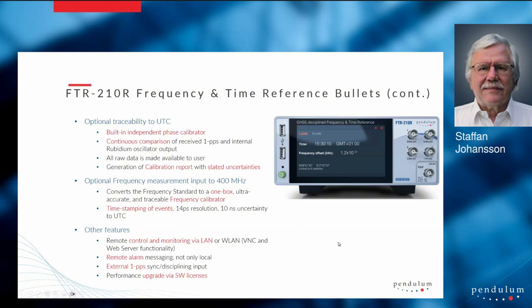There are other important bullets to mention, most of all the optional traceability to UTC, because this is a unit where you can get true traceability to UTC thanks to a built-in independent phase calibrator that makes continuous and gap-free comparison of the received 1 PPS signals from the satellite and the internal Rubidium oscillator output. All raw data is made available to the user, and it can also generate a calibration report with data and stated uncertainties.